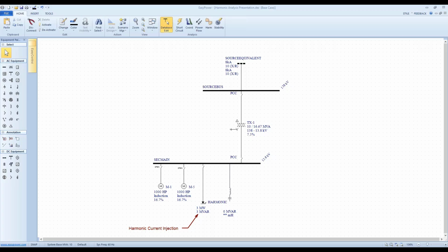When you do have capacitors in the plant, the resonance issue will most often show itself as blown fuses on the capacitor bank. Very high voltage distortion, sometimes 20–30%, may also show itself. If you have high distortion, the transformers will tend to be much louder, which is another sign of harmonics within the plant. And then, of course, there is the heating effect of harmonics within transformers. If the load is not beyond the rating of the transformer, but the transformer is running hot, it would typically be a sign of high harmonics.